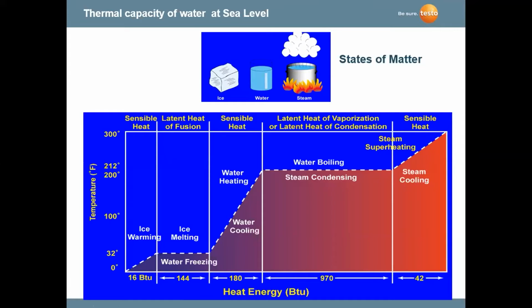And as we change at 212 degrees and at sea level, which is 14.7 psi, the water temperature does not rise. What happens is that we have a change of state. We're going from a liquid to a vapor, and that's where you get this straight line right here, until we reach a point where we transition to all vapor. And when we transition to all vapor, then we start heating up the vapor. And this is where you see the line here above 212 degrees. So what you see here on the top right is called superheat. And on the liquid side, when we're removing heat from water or a refrigerant, that's where we have subcooling.